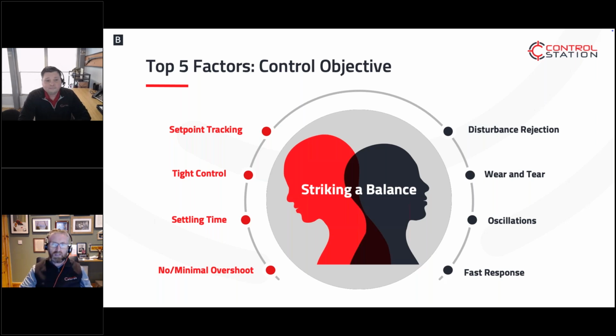It sounds deep and meaningful, but the reality is, when you're standing in front of a PID, why am I here? What has brought me to this point? Whether it's a new loop that you're commissioning, or it's a loop that operations have brought you over to say that PID is not working anymore. Well, you have to answer all of those questions as to what is it not doing, what is it not achieving.